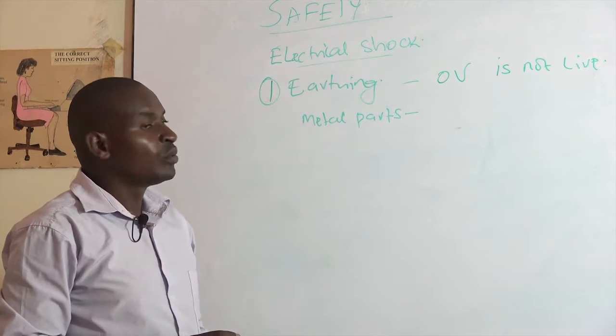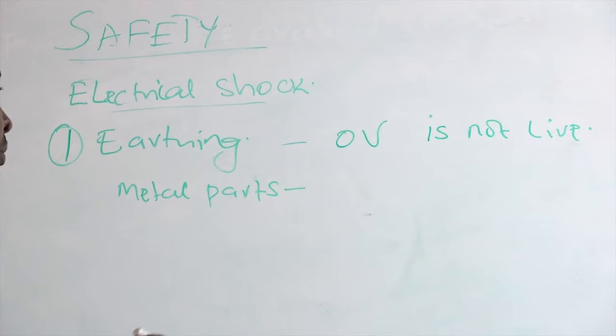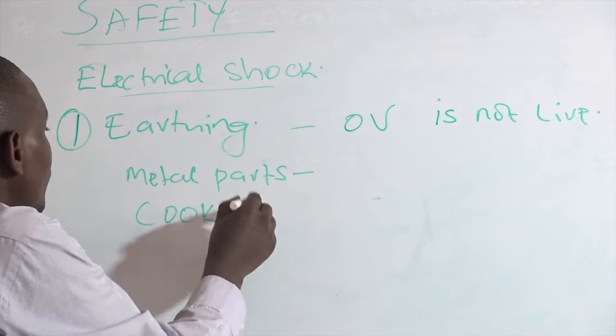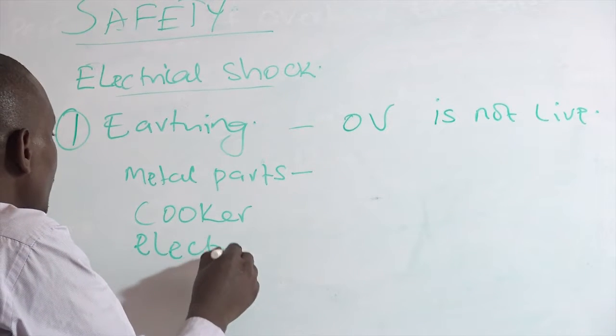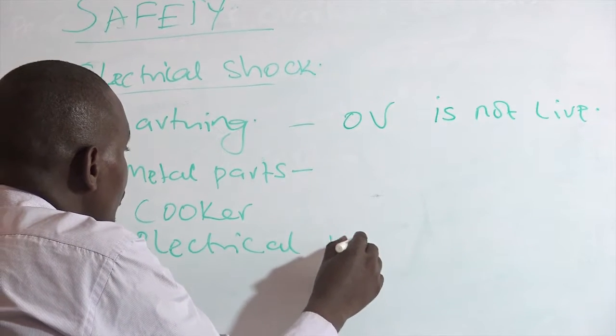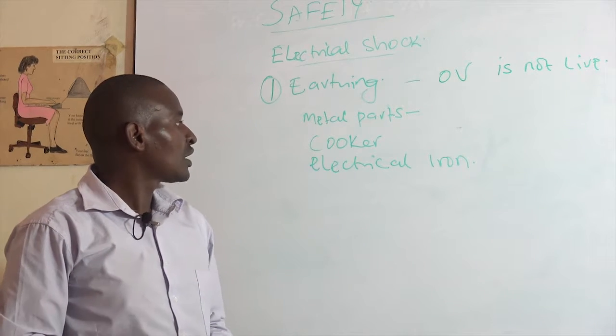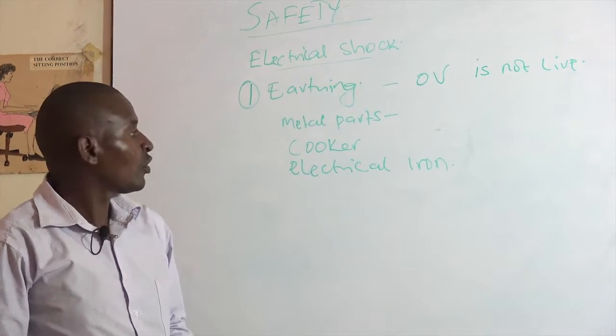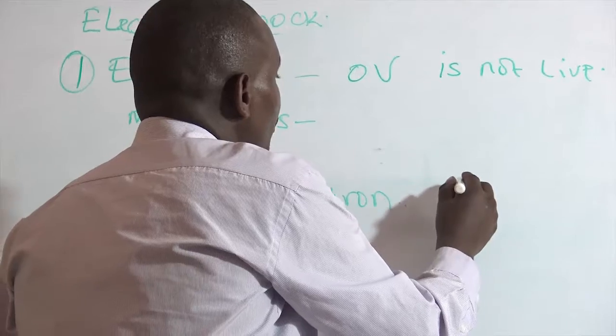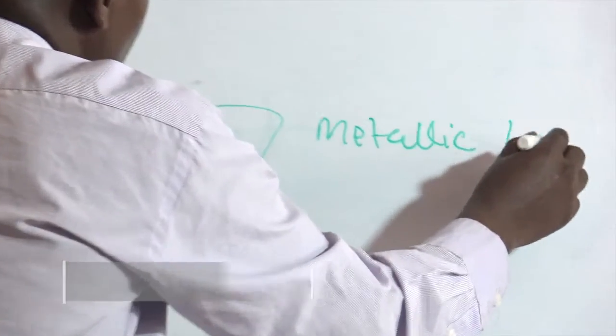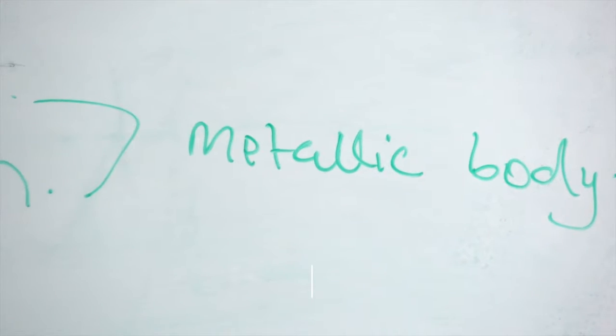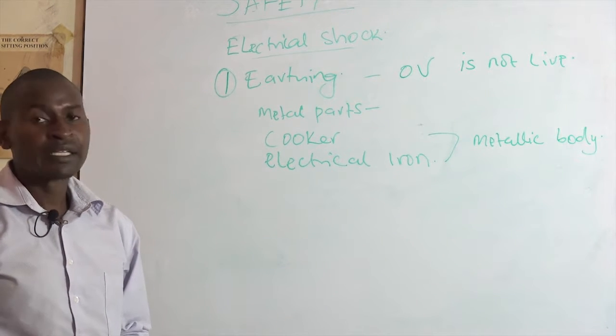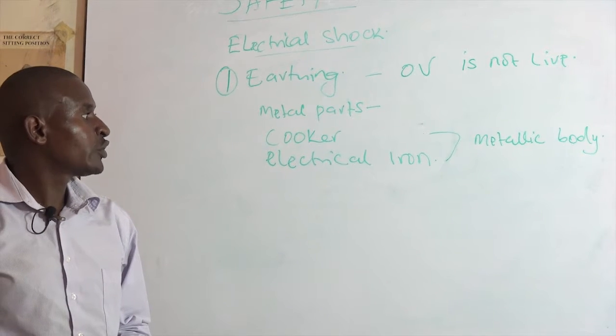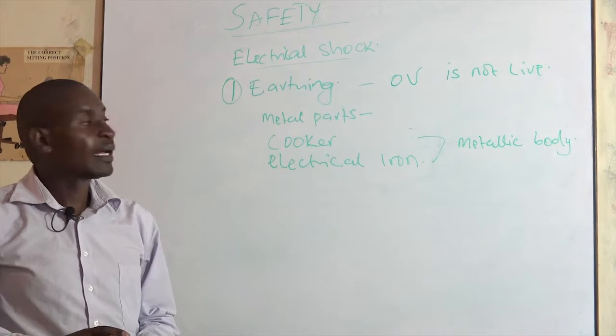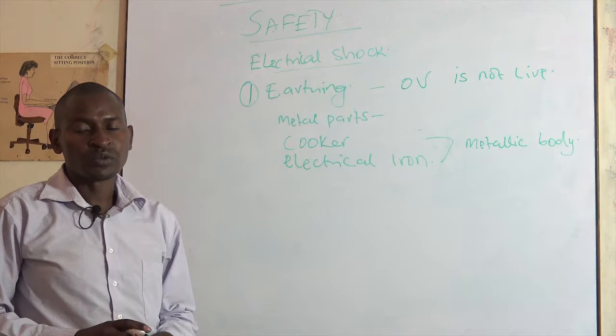This is what happens when you have an installation with something like a cooker or an electric iron. These equipment, though they use current, have a metallic body, or a frame that is made of metal. And from what we know, all metallic parts can be electrically charged. So we have to take caution so that even if these metallic parts are electrically charged, they remain at zero potential. This is what is done.